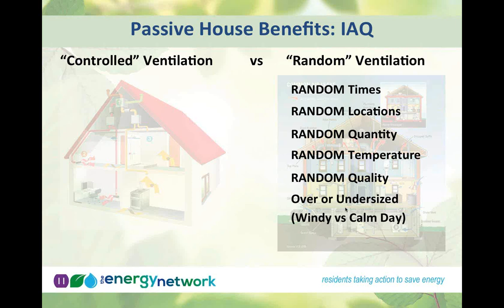This whole system, if you want to call it a system, is mostly either over-ventilating or under-ventilating. There may be a few days a year where it's giving you exactly what you need, but that's simply coincidence. It has nothing to do with how many people are in the building or what's going on in there. It's more about whether there's wind blowing and whether it's cold or hot outside.